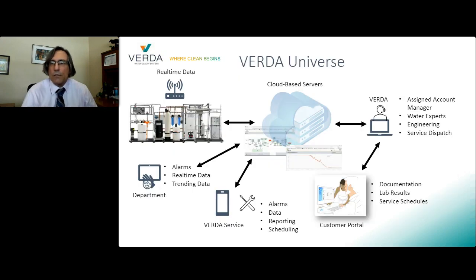So if we look at the water quality management plan from the top level, this is what it looks like. The equipment is sending real-time data. Some of the data is fed back to the user and our technicians, who access it on smart devices or browsers. Alarms are triggered if something is trending or has gone out of specification so that our technicians can take action. Monthly, we go into the department and take water samples that are either tested on-site or sent to the lab. Monthly, all the data we collected and testing we have done are summarized in reports that demonstrate the customer is complying with AAMI TIR34. Again, this can be done in a completely manual process. It just requires more people work.